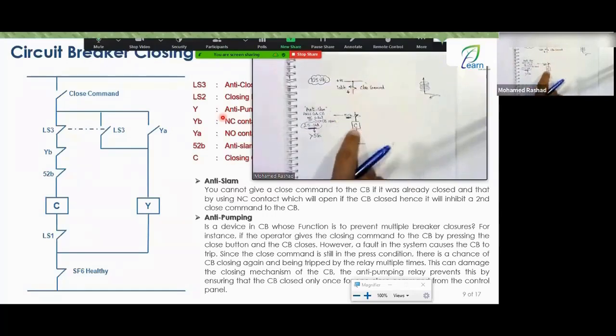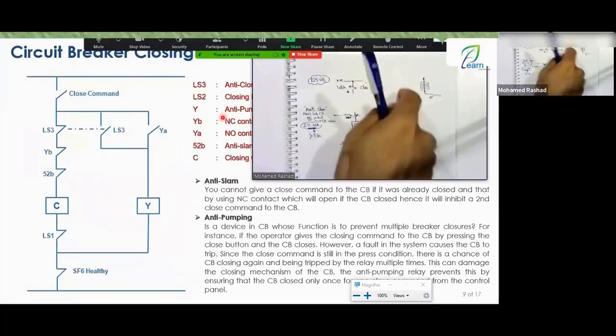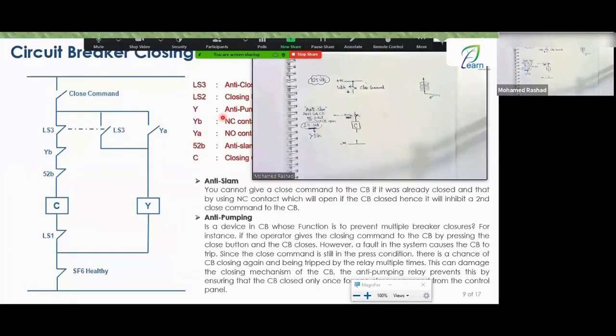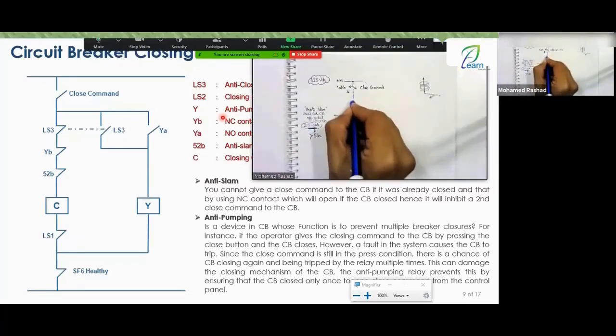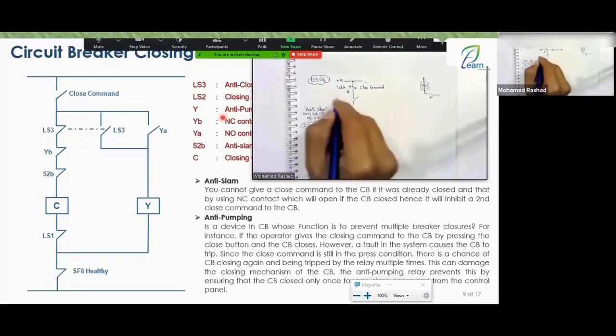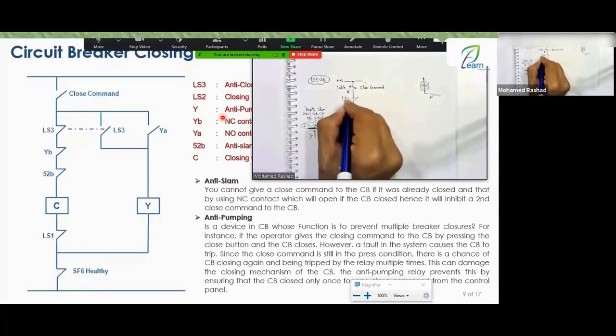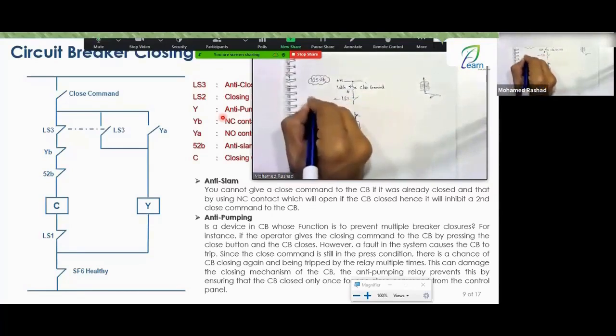And you gave the close command to the breaker. If you gave the close command, mechanically, the breaker will not close because the closing spring is not charged. You are connecting the DC to the close coil, so you will burn it. Right or wrong? I told you. So I have to take a normally closed contact called LS3 from the spring state, the CB spring.